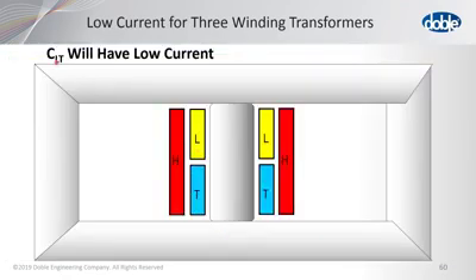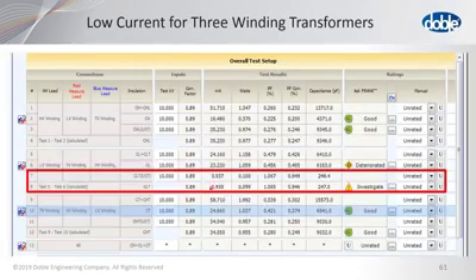Now this is another situation that we found where the CLT will have a low current. The reason for this is because this is a stacked winding. Often these two windings will have the same rating, 4160 volt. It's an auxiliary transformer at a power station. And the reason this has a low current is because the capacitance is very low here. The area between these two windings is very small compared to between high and tertiary and high and low. Here's an example of that. Again, under 1 milliamp, and notice that it's very consistent though, so there's really no problem, but it's a lot lower than the other currents. Notice also that these currents here and here are very similar because those areas are very similar. So this, again, is not indicating a problem, it's indicating a particular construction of the transformer.